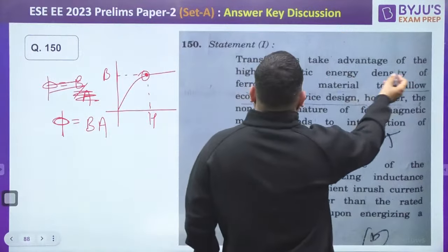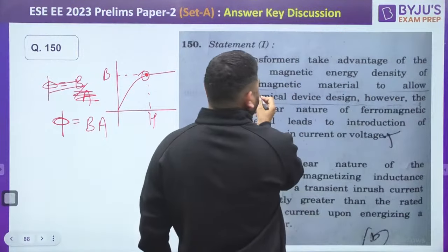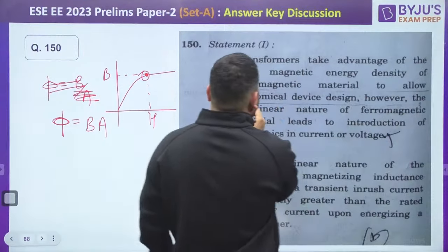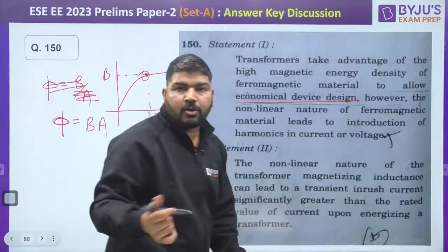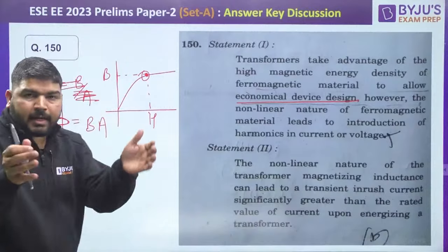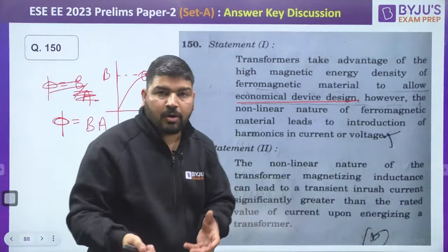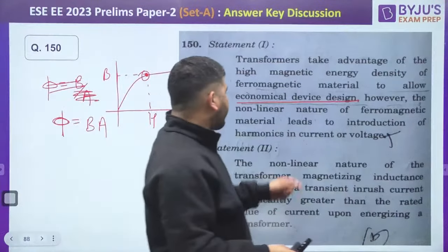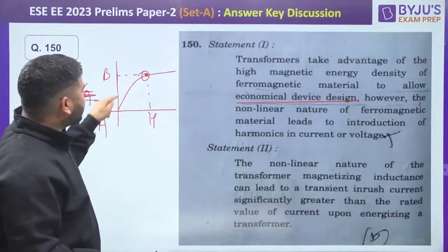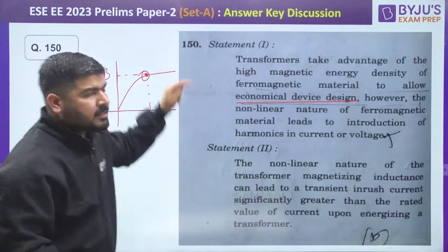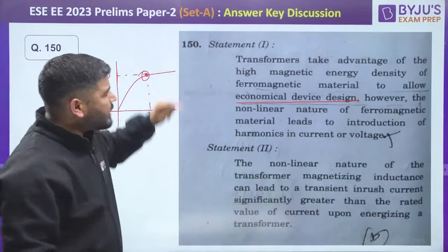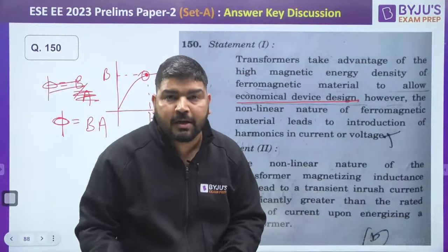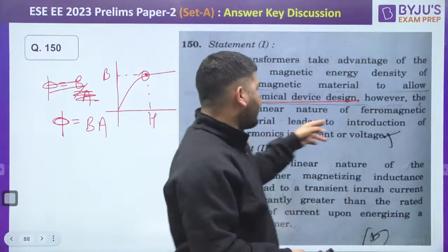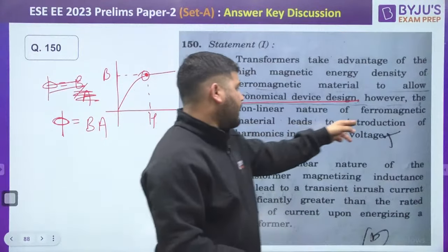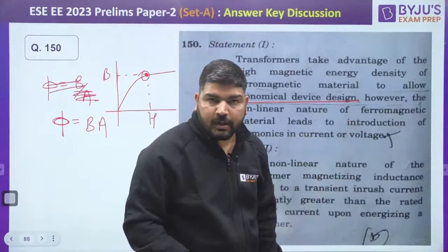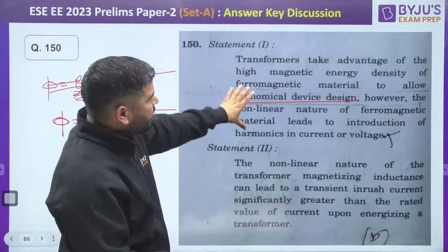The transformer takes advantage of the high magnetic energy density of the ferromagnetic material to allow economical device design. It means your money is saved because the core cross section area is reduced, so less core is required. Because of this, it goes into the saturation region, and if it goes into saturation, harmonics will be introduced in the current and the voltage. So statement 1 is correct.